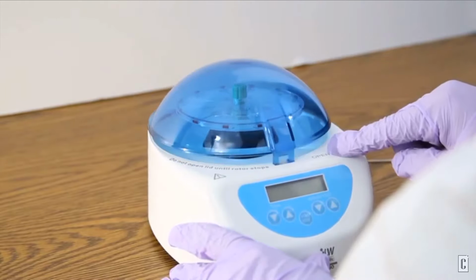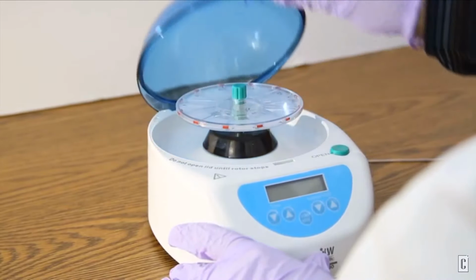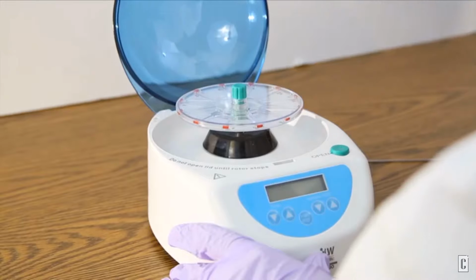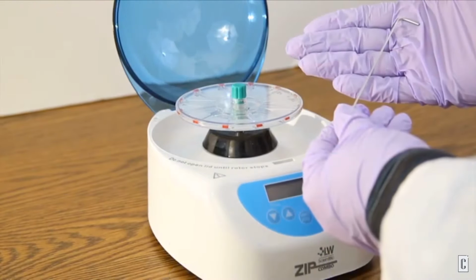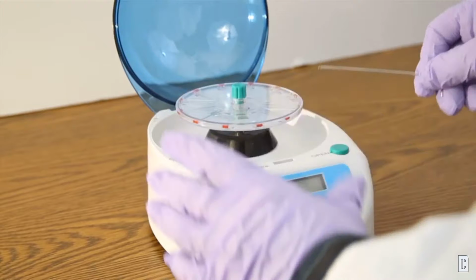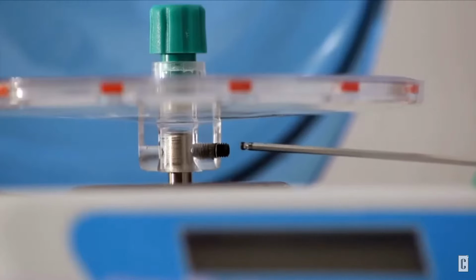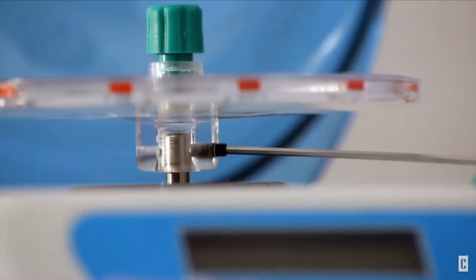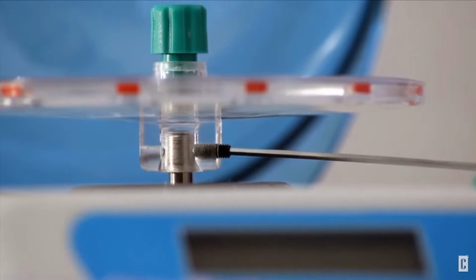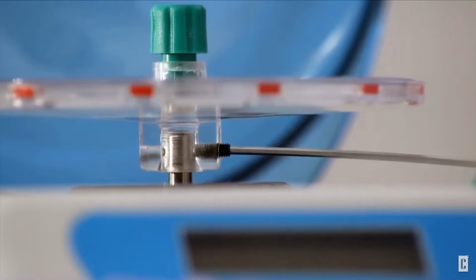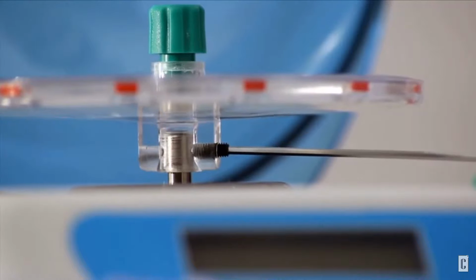Determine whether the desired rotor is installed and ensure that it is secured tightly to the motor shaft. The included Allen wrench can be used on the underside of the rotor and inserted into the set screw. Turn counterclockwise to loosen and change the rotor, and clockwise to tighten the rotor that slides over the motor shaft. The rotor must be tightly fastened, but do not over-tighten.